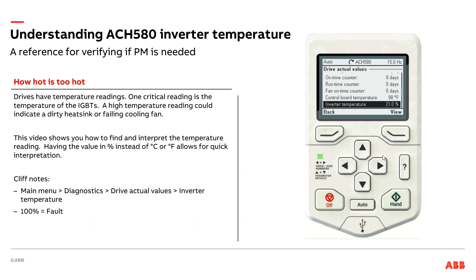What you want to do is — this is the type of data that's okay to check manually just like we did, but it's an awesome data point for you to trend over BACnet or through your building automation system. Because over time, you can look at the temperature profile of the drive. If you take snapshots during the peak loading period so you have similar loading from one day to the next, and you see over days, months, or years that the temperature just keeps creeping up higher and higher — that's a really good indication that this drive is not cooling itself as well as it used to. Maybe it's dirty, maybe there's a fan issue. These are triggers to let you know to look at that drive.